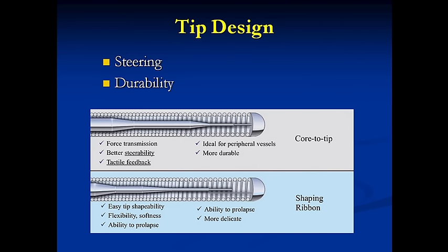So what's the difference? With a core tip, it's usually very good to use in peripheral vessels, simply because we go up and across - there's a longer distance we traverse, so you need better steerability, and most importantly you need the tactile feedback, especially when crossing CTOs. Unlike that, the shaping ribbon provides more flimsiness or flexibility, and it tends to prolapse more easily, and you don't get as much tactile feedback because of the cushioning between the distal end of the core and the shaping ribbon.